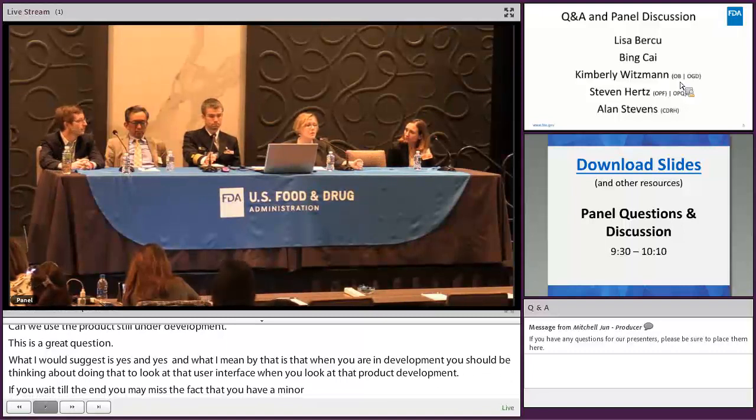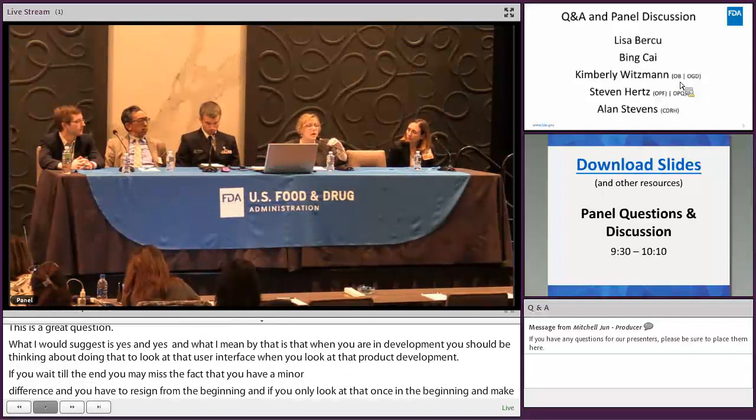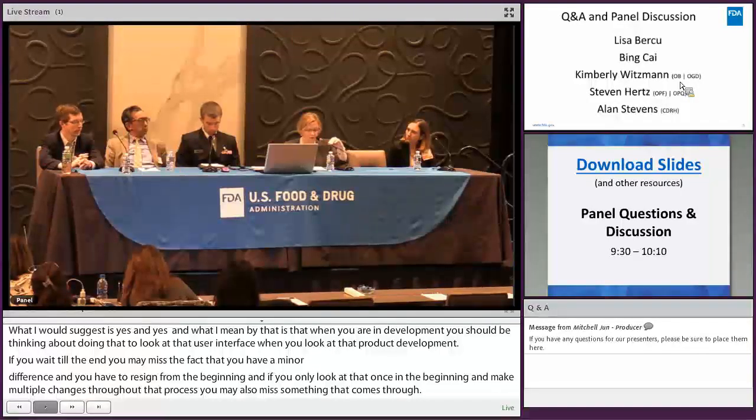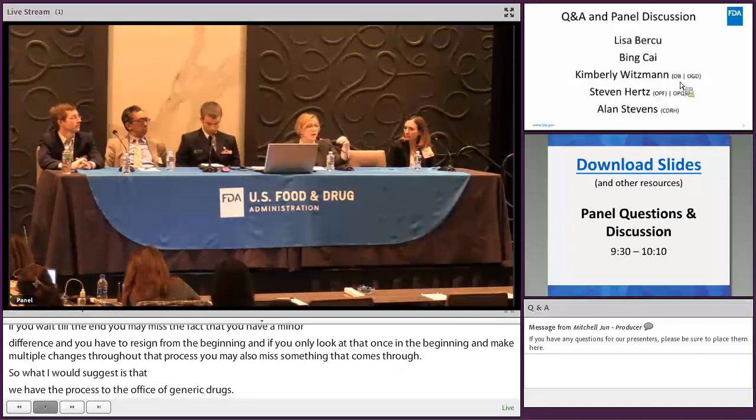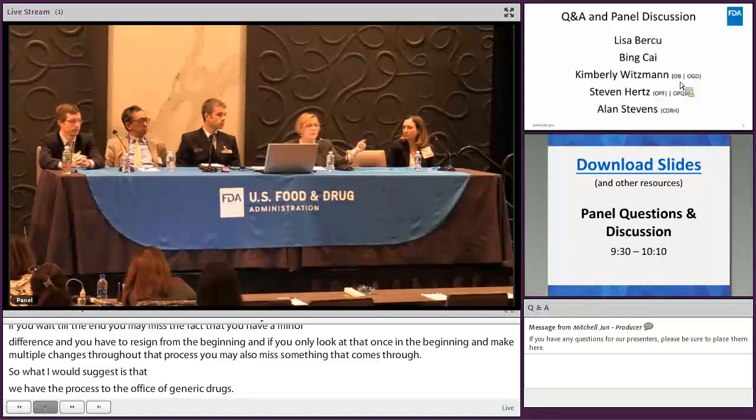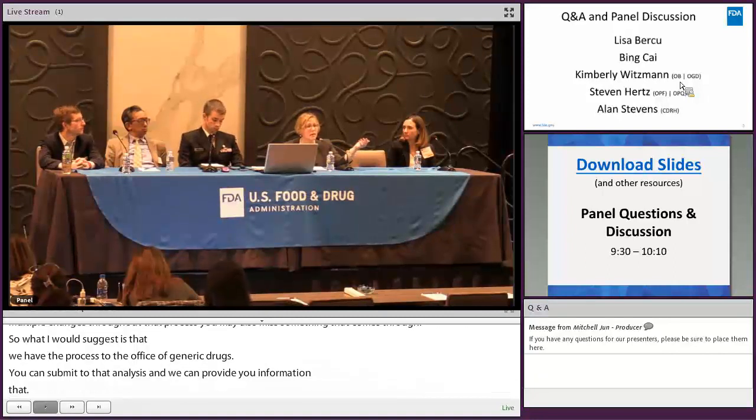So what I would suggest in that case is that we have a process by which you can submit a controlled correspondence for your device user interface assessment to the Office of Generic Drugs. You can submit to us your comparative analyses, we will take a look at them, and we will provide you information back in a controlled correspondence. There's a 60-day clock on those device user interface assessments, so you can get answers back within 60 days, which for the FDA is kind of fast. So that's one way that you can have an assessment of that.